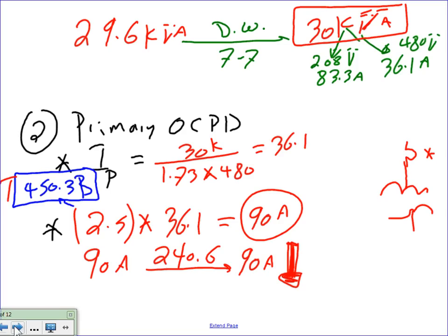Here's your option number 1. Either you go down to 90, or you custom design a fuse and pay an arm and a leg for it for 91, or you go to the bar, drink, and cry because you could not find your fuse or circuit breaker. The third one is mine. Any question, guys, about this? So if it doesn't allow you to go up, the default is you go down because you can't stay where you are. Can I go to the next one, Dustin?